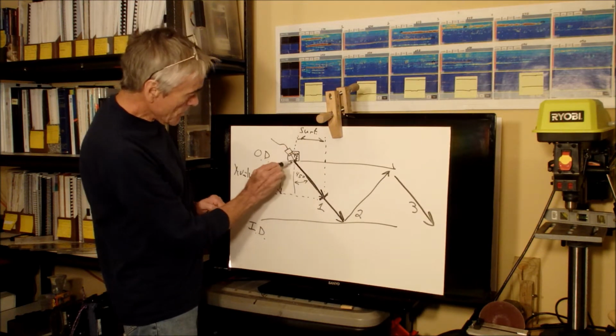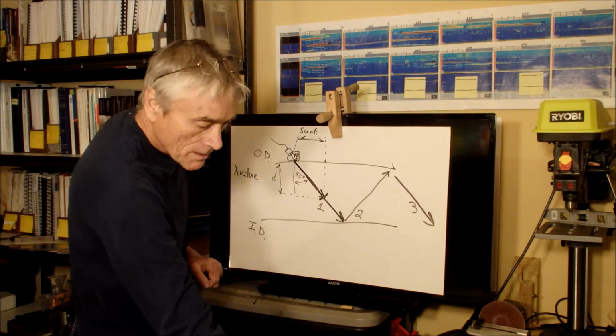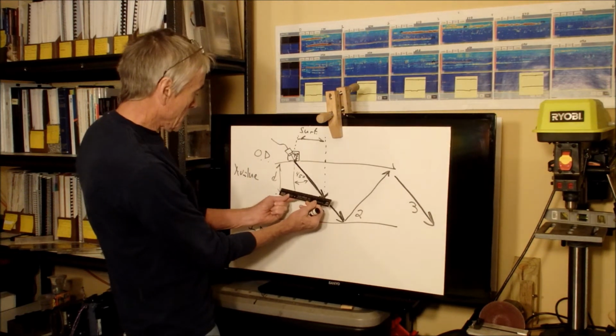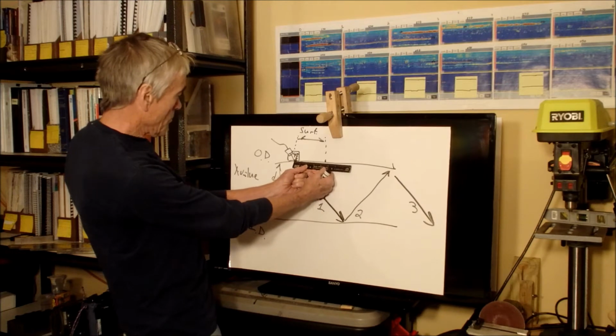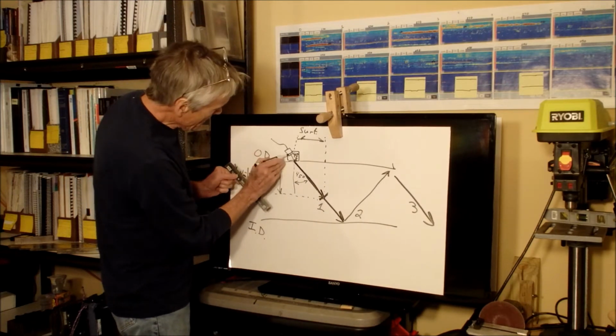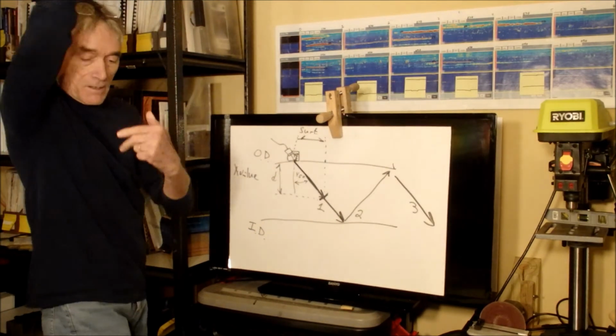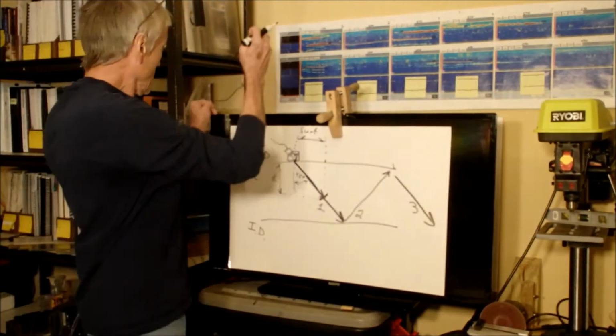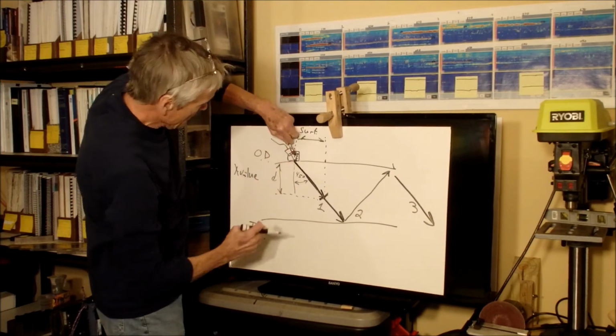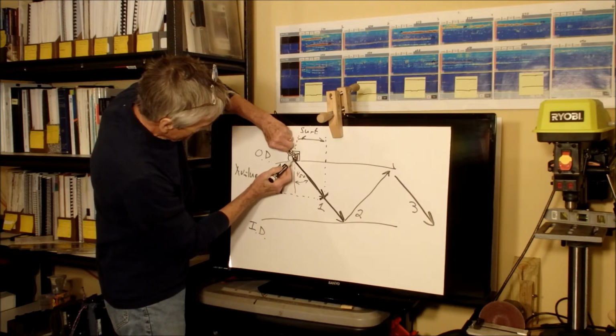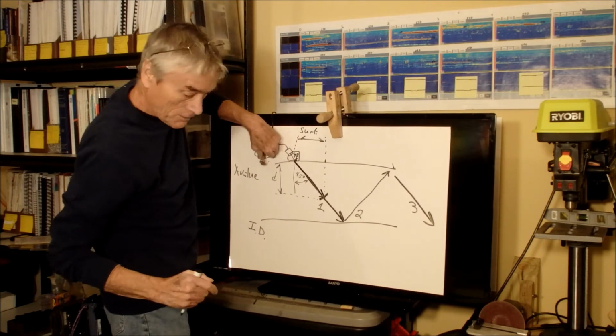And if we try to measure from that index point, it can be kind of difficult. It's going to look easy here on the chalkboard, but sometimes it can be difficult to see where that index point is. This is what an actual 45-degree search unit looks like. It can be pretty hard to find that little point right there.